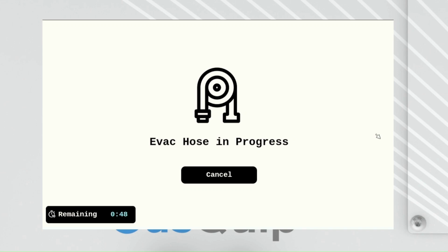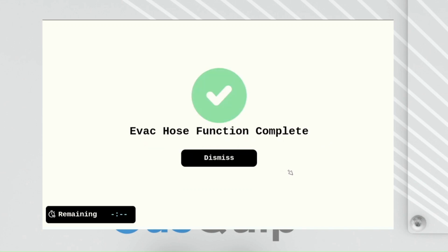So you'll hear the pump kick on for a few seconds, and then the system is going to check that hose for leaks once the actual evacuation has pulled on it. So it's checking to see if the vacuum is rising back to 0 psi or towards 0 psi to see if there is a leak. And if it is not, then it'll give you a pass. And if it does rise too much during that amount of time, then it'll fail the test, and you'll have to either retry the test, or if you fail again, you might have a leak on your hose.